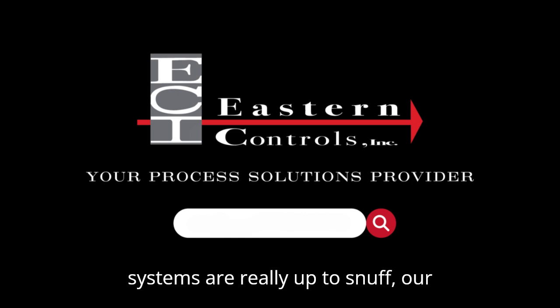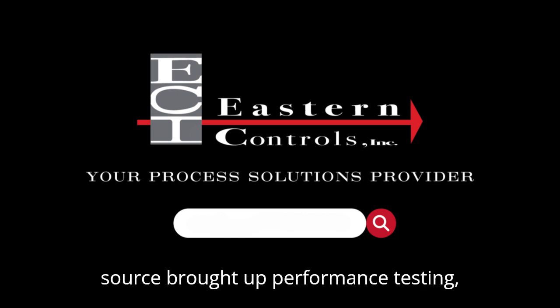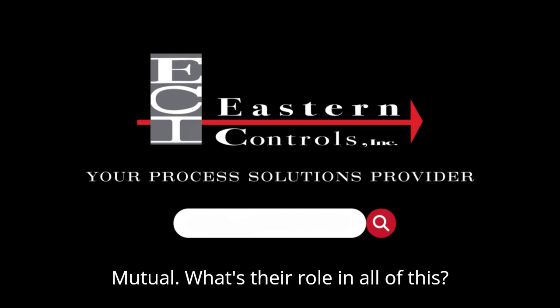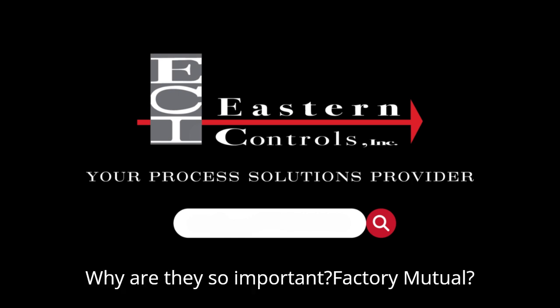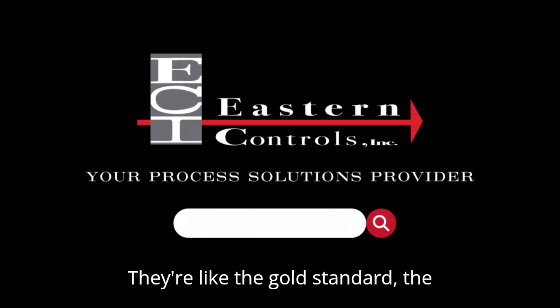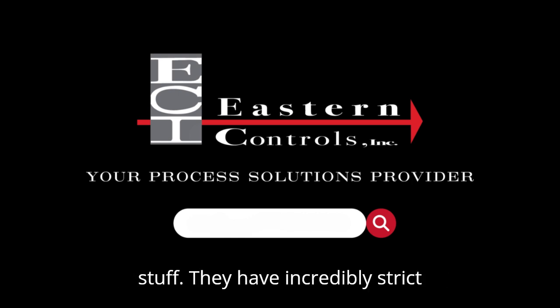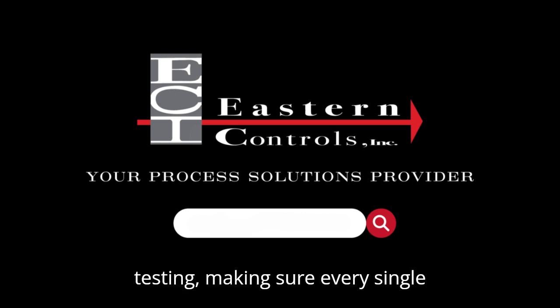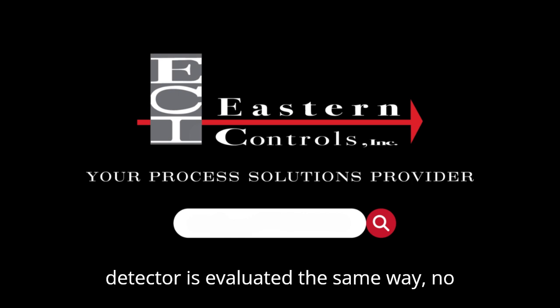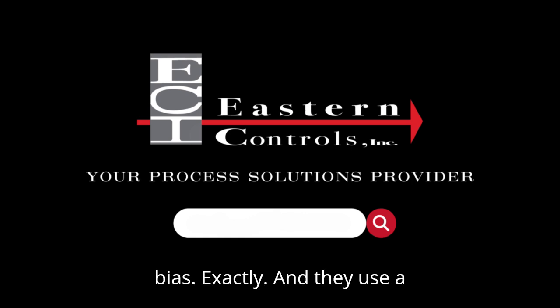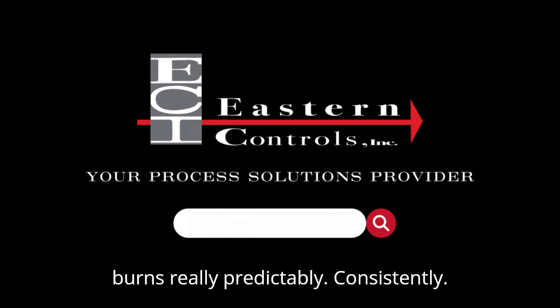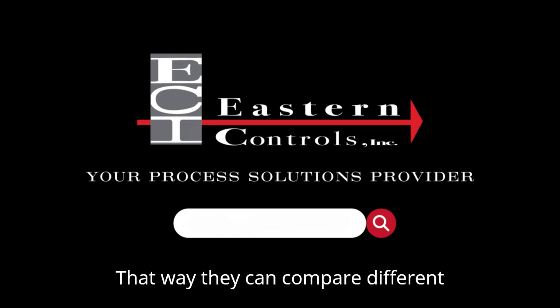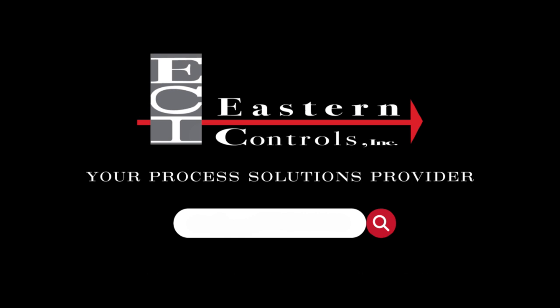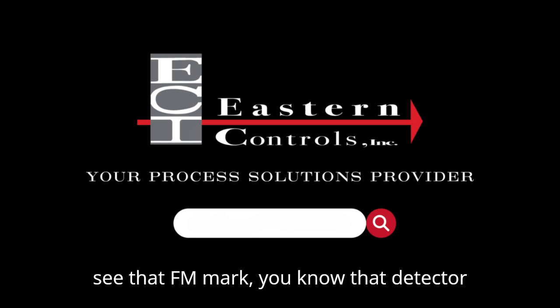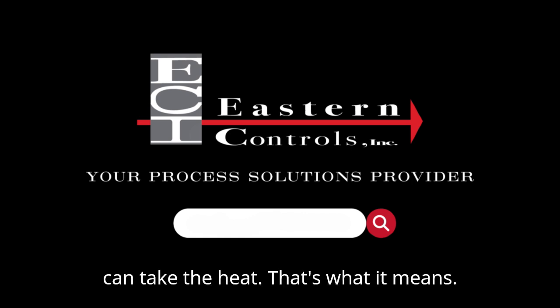And to make sure these systems are really up to snuff, our source brought up performance testing, specifically mentioning FM, Factory Mutual. What's their role in all of this? Why are they so important? Factory Mutual, they're like the gold standard, the independent auditors for this kind of stuff. They have incredibly strict testing, making sure every single detector is evaluated the same way, no matter who makes it. So it eliminates any bias? Exactly. And they use a standardized fuel, n-heptane. It burns really predictably, consistently. That way they can compare different technologies, different manufacturers, all on a level playing field. So when you see that FM mark, you know that detector can take the heat. That's what it means.